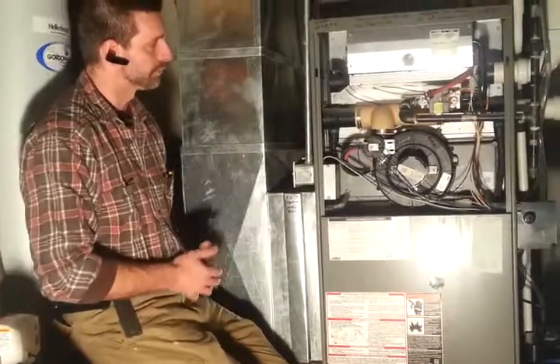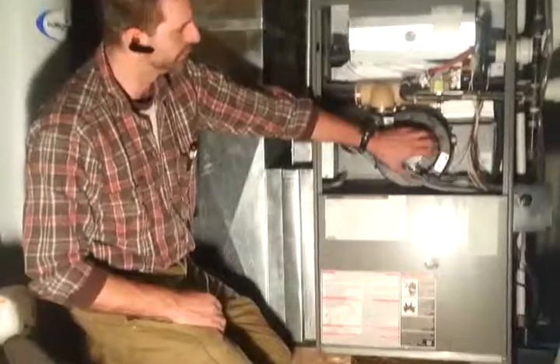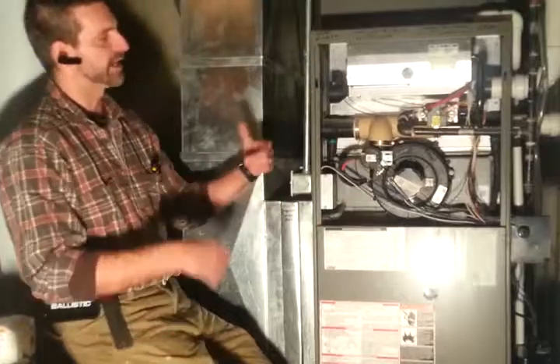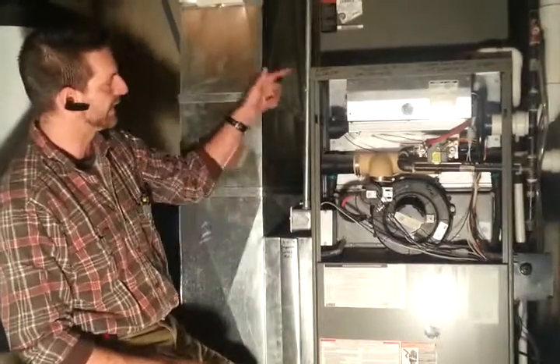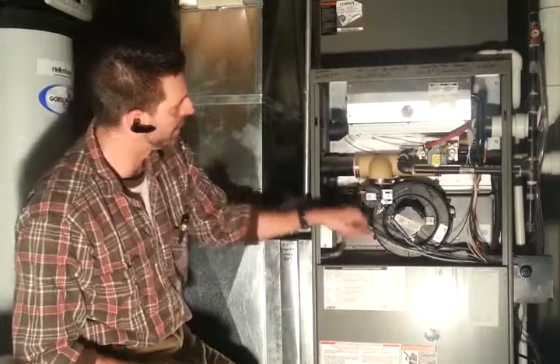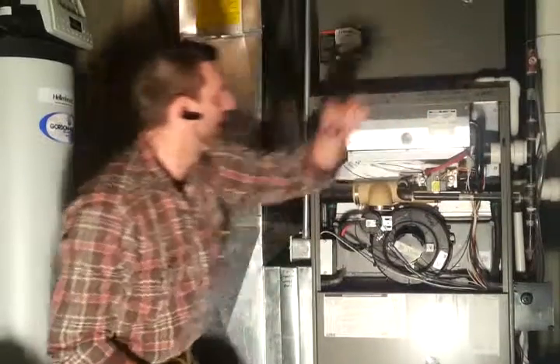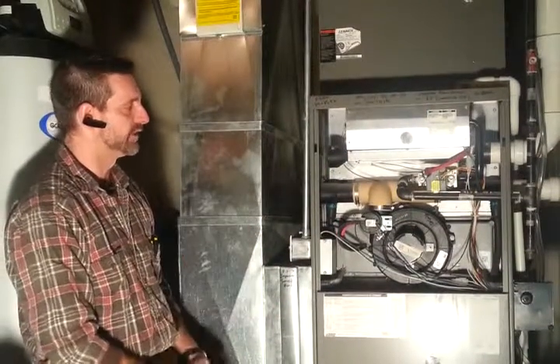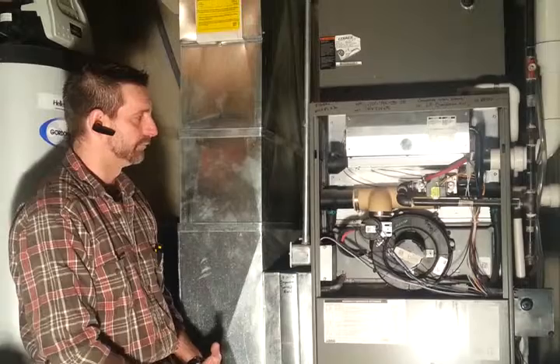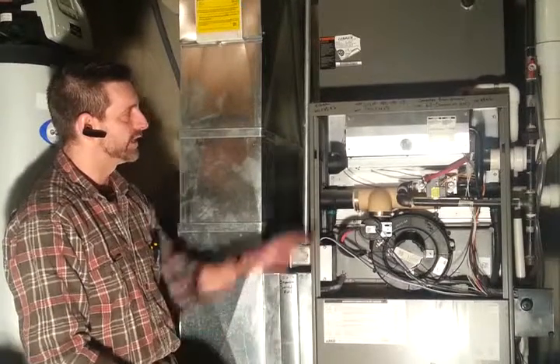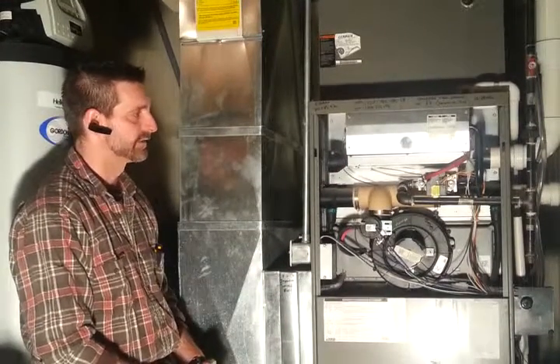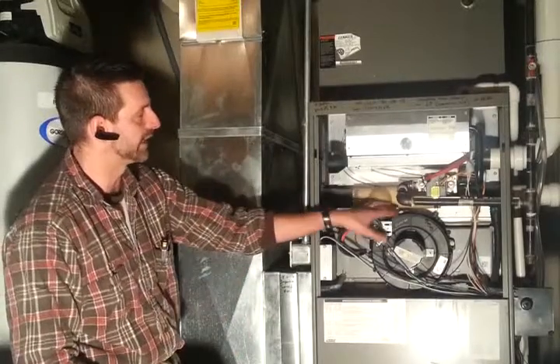Let's talk about some of the major components here. This is what we call the induced draft motor, and its job is to take all of those flue gases out of my heat exchanger. It's going to pump them up and out of the house. So that's how we get rid of the flue gases, any uncombusted gas, any carbon monoxide. That's all taken out here.